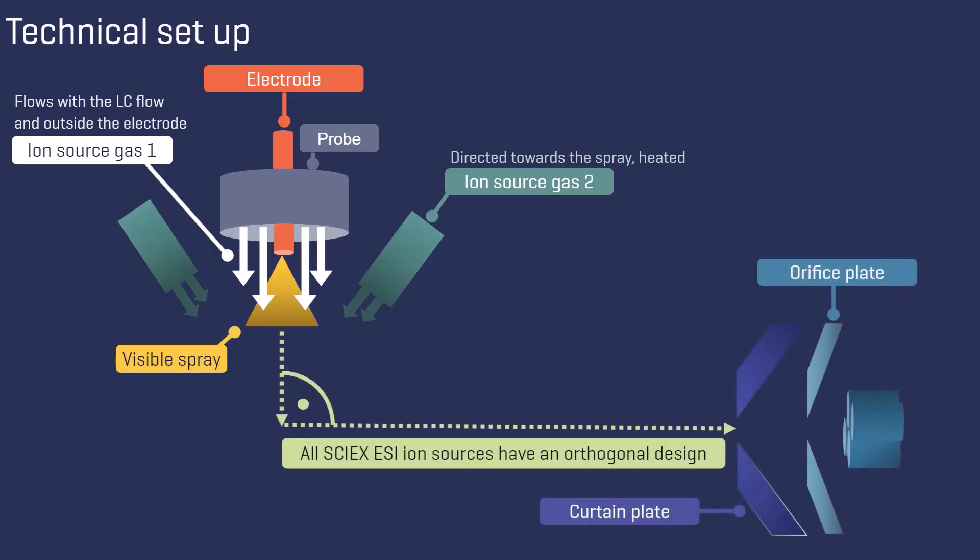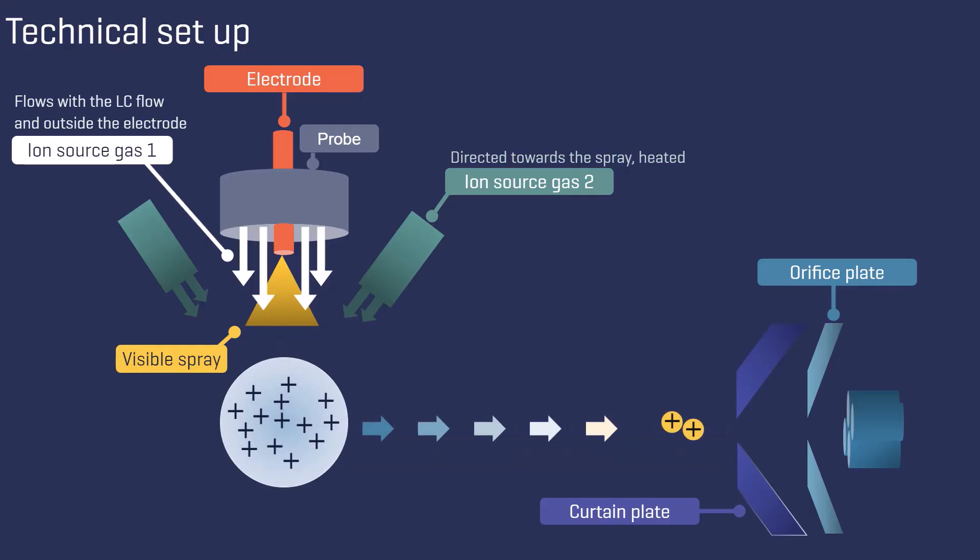All SCIEX ion sources feature an orthogonal design, where the electrode and the entrance to the mass spectrometer are positioned at a 90 degree angle to each other, as illustrated. The droplets undergo the coulomb explosions and the bigger droplets can be removed easily due to the design of the source.